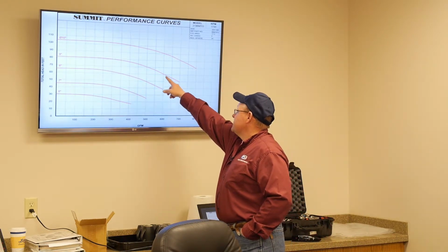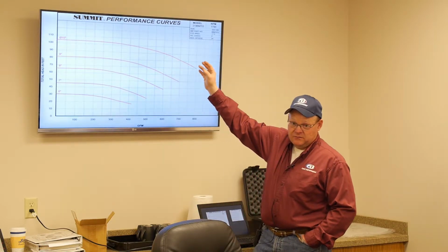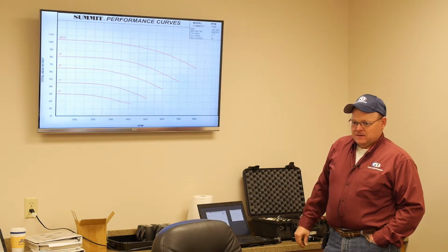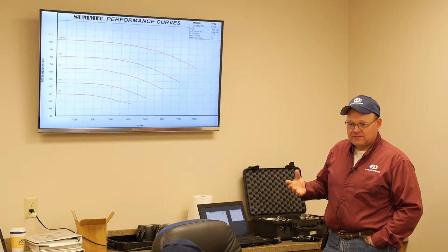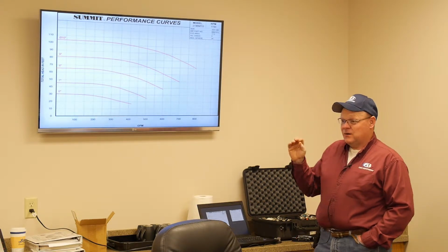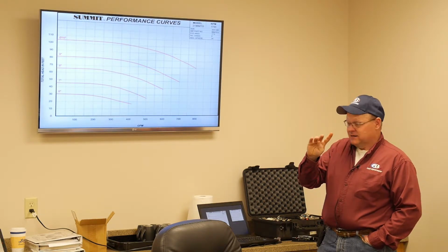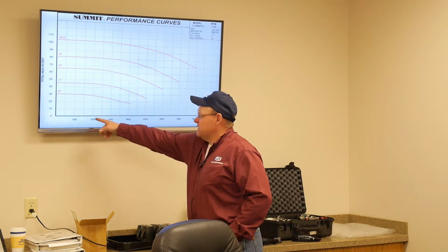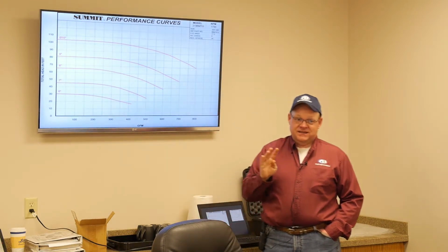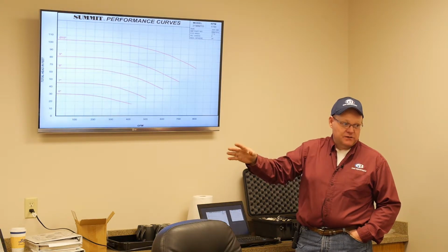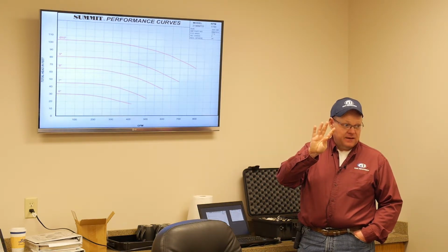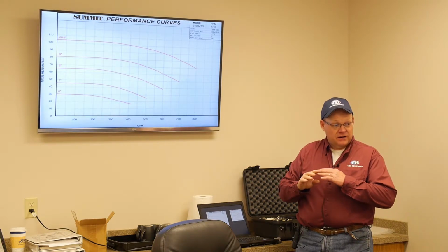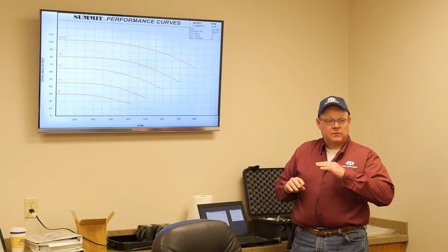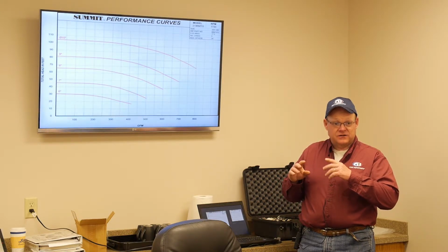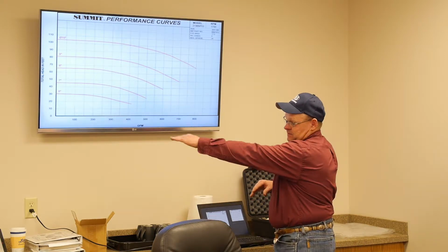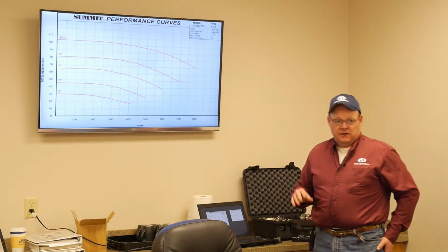So now we're going to go back to 600 at 60 feet divided by 2.31, which is roughly 25. What'd you say? 25? 25.97. Okay. So now we only have 4 pounds difference, right? 4 pounds between 600 gallons a minute and 200. You can change 4 pounds in a system quick, easy. You can triple the flow with just 4 pounds. And this gets even worse when you get into an impeller curve that is flatter. In other words, like a 2 by 1 by 10, 2-inch suction, 1-inch discharge, 10-inch impeller. That curve will look like almost a plateau. There'll be no curve to it at all.